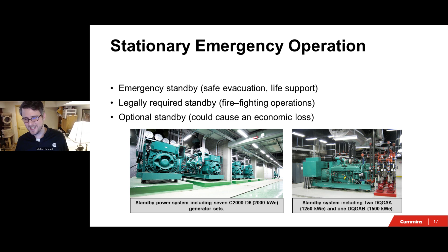So that's the EPA's definition. If you turn on that generator set only when the normal source has failed, it can be considered emergency. It doesn't matter if that's serving life safety loads. It doesn't matter if that's serving legally required loads. It doesn't matter if it's serving optional loads. So it could be anything from a healthcare facility to a data center. The EPA says it doesn't matter. If you're turning it on when the normal source of power fails, it is emergency.